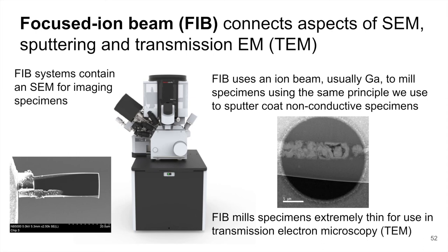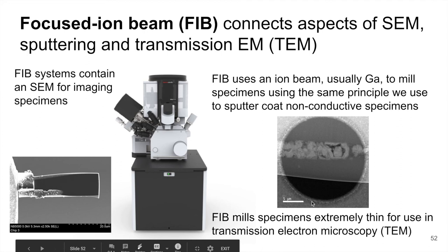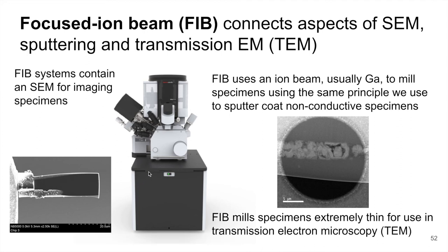I want to mention one last thing about SEM — Focused Ion Beam, or FIB — because it bridges the gap between SEM, which we're talking about now, and Transmission Electron Microscopy, or TEM, which we'll discuss next. The FIB process is used in TEM to prepare specimens, but the FIB system also functions much like an SEM, with an imaging component as well as a sample preparation component where we can actually manipulate and change the shape of samples.